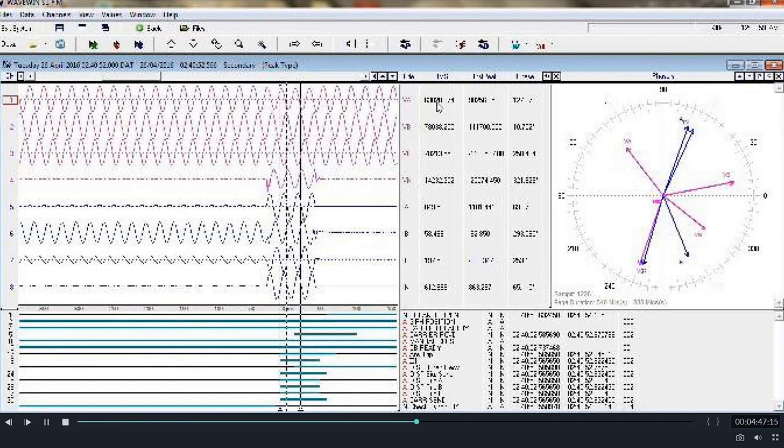So if we look at the DR before the 0th time, that is 0 millisecond, and after 0 millisecond, we will be able to observe what activities happened in the relay because of the fault. We will be able to see that during the fault the current has increased, as the graph of current has bigger spikes, and the voltage was reduced during the faulty condition.